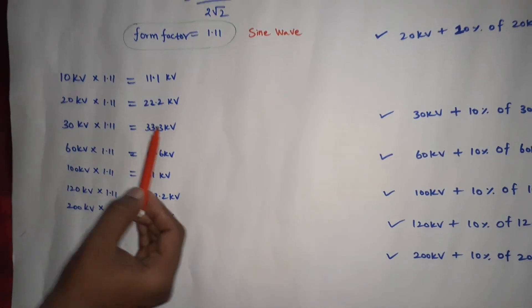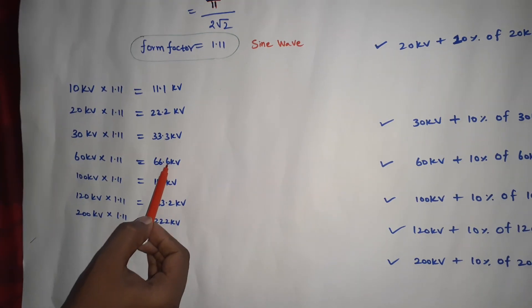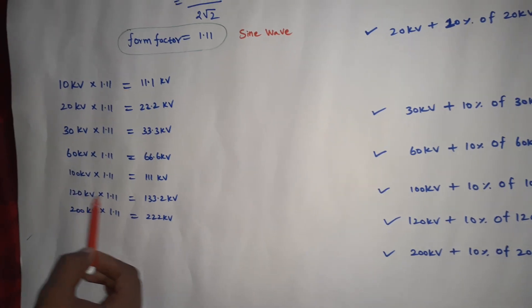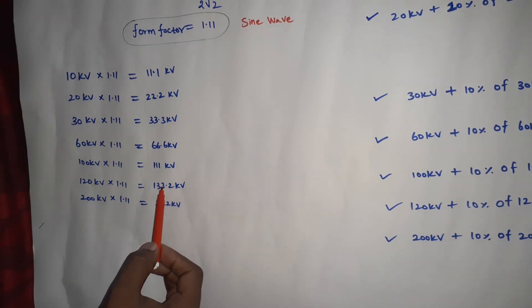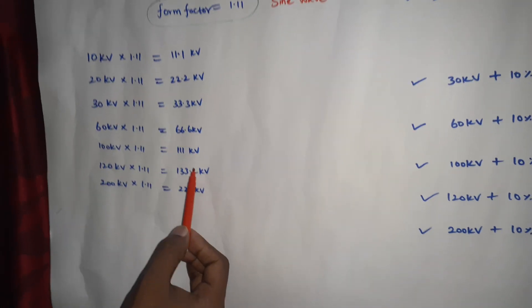If you look at 60, this is one variation. 60 times 1.11 equals 66 KV. If you look at 120 KV times 1.11, it is 133.2 KV.